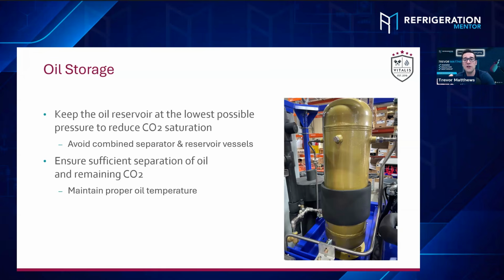Do you have any recommendations? I'm sure you've seen this before, where all of a sudden your flash tank loses control, it gets too low, and now you lose your oil pressure. You want to talk a little bit about that and some strategies for technicians to look out for? Yeah, that mostly depends on the liquid receiver pressure. There are some ways to maintain the liquid receiver pressure inside the controller typically, so it forces the high pressure valves to open to drain more of the high pressure coming from the gas cooler to maintain the receiver pressure.